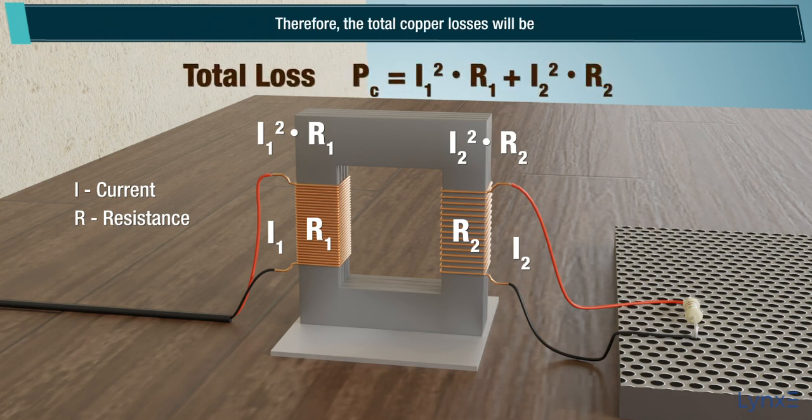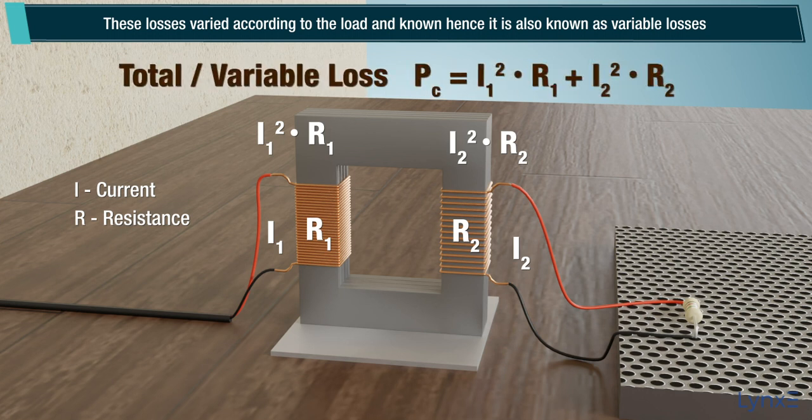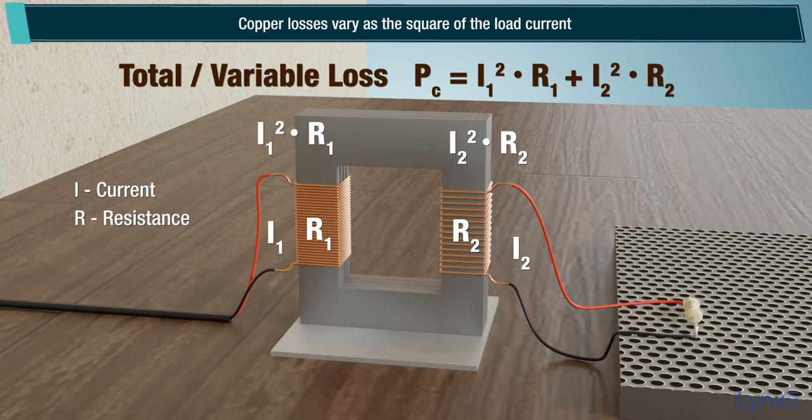Therefore, the total copper losses will be the sum of both. These losses varied according to the load and hence it is also known as variable losses. Copper losses vary as the square of the load current.